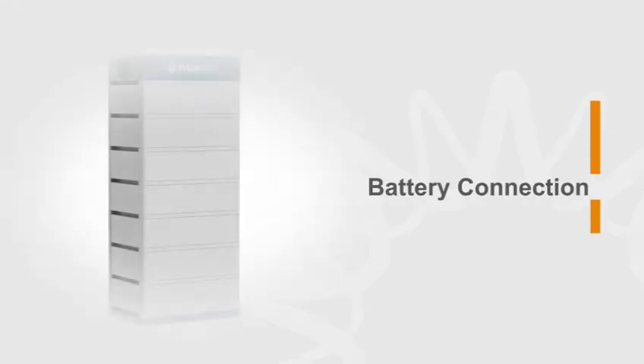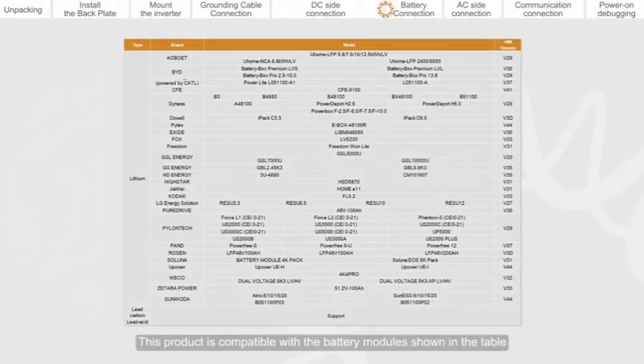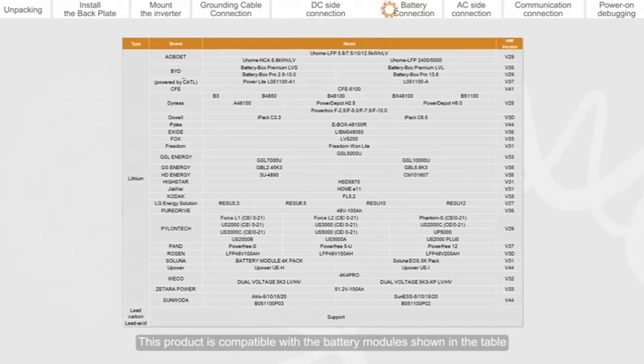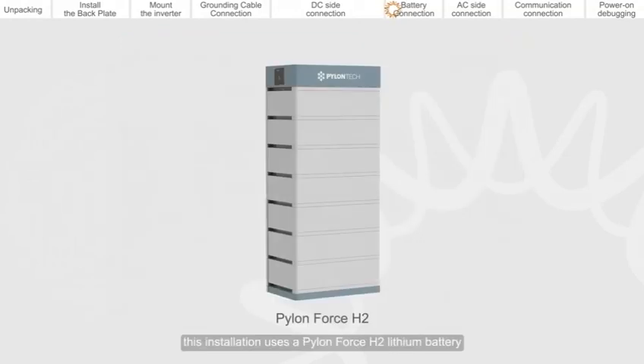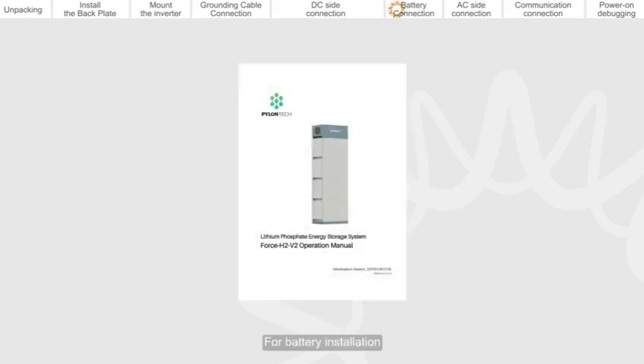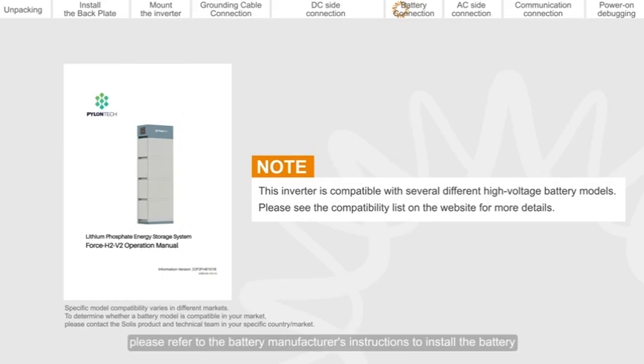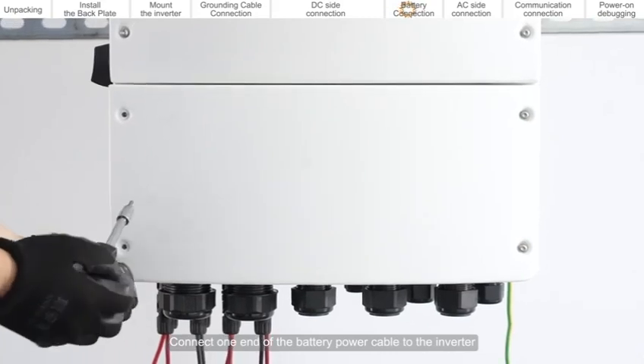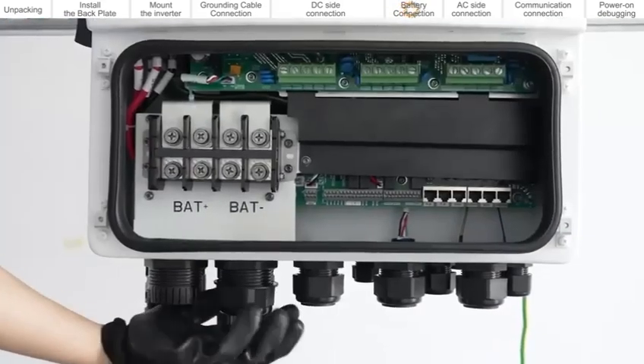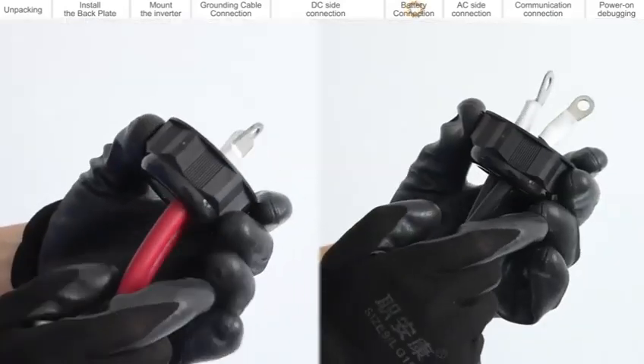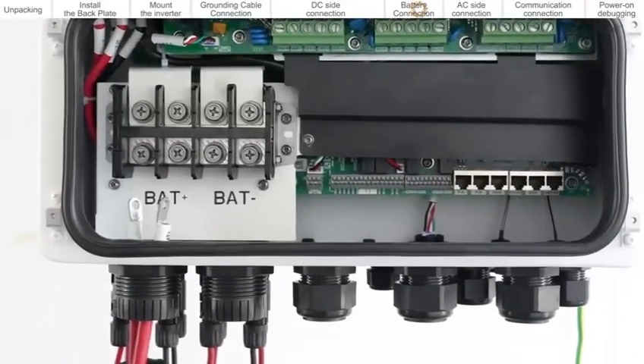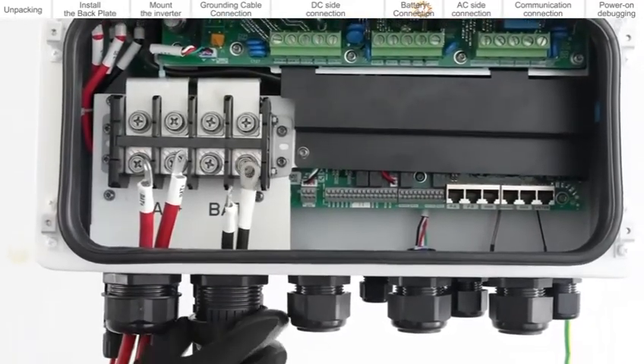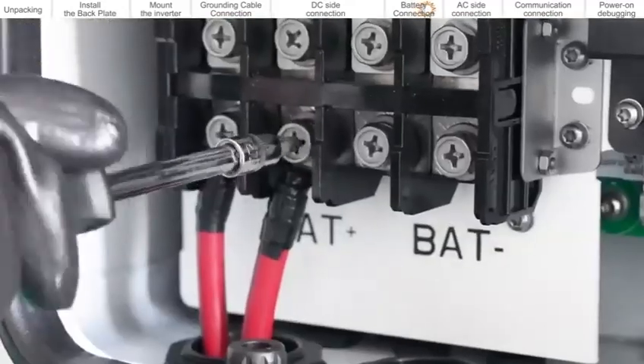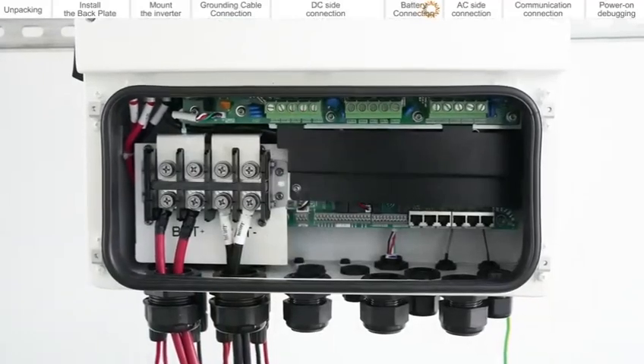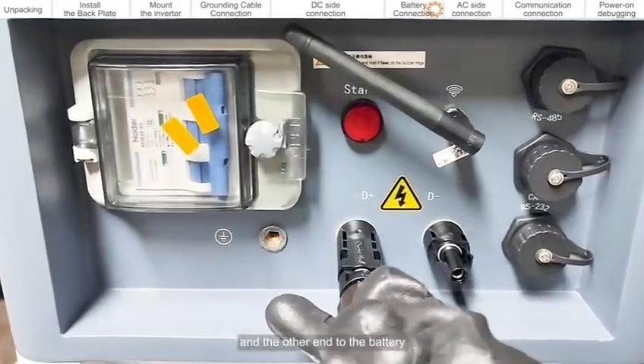Battery connection. This product is compatible with the battery modules shown in the table. This installation uses a Pylontech Force H2 lithium battery. For battery installation, please refer to the battery manufacturer's instructions to install the battery. Connect one end of the battery power cable to the inverter, and the other end to the battery.